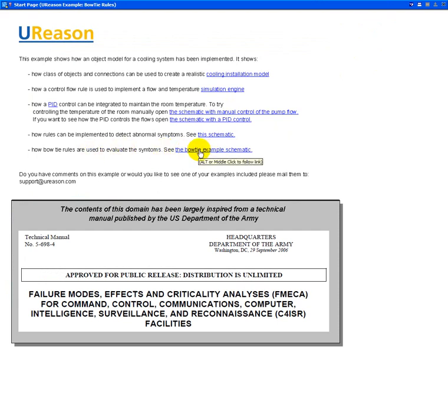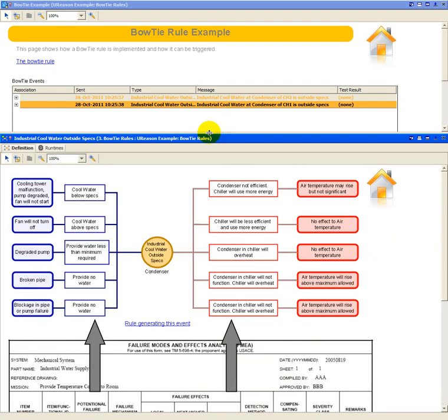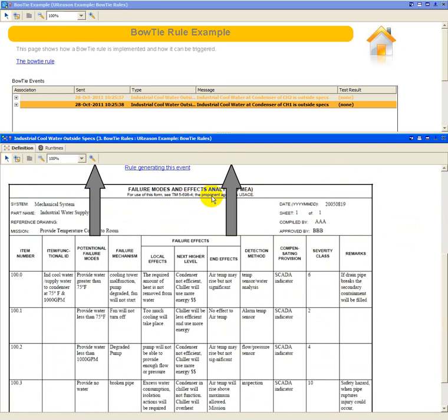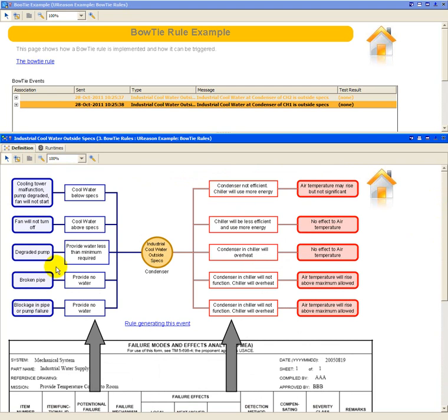The last part of this demonstration is about the bowtie rule. Go into that right now, and I'll click here to show you the implementation of the rule to start with. It's completely inspired from the failure modes and effects analysis form that's been described in the US Army document. So, for instance, all these potential failure modes or effects here have been reproduced into this rule here. So this rule, the central point of this rule is an event, an incident, in this case the fact that the industrial cool water is outside a specification for a condenser. It's a generic rule. If that is the case, then the rule will be triggered and look at the possible causes for this outside spec event. And that is listed by all these blocks here.